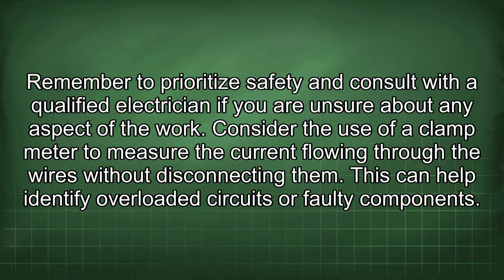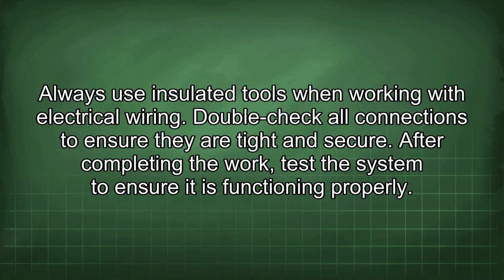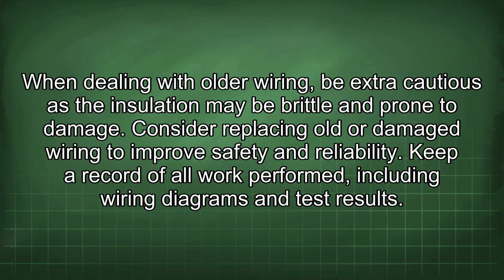Consider the use of a clamp meter to measure the current flowing through the wires without disconnecting them. This can help identify overloaded circuits or faulty components. Always use insulated tools when working with electrical wiring. Double-check all connections to ensure they are tight and secure. After completing the work, test the system to ensure it is functioning properly. When dealing with older wiring, be extra cautious as the insulation may be brittle and prone to damage. Consider replacing old or damaged wiring to improve safety and reliability.